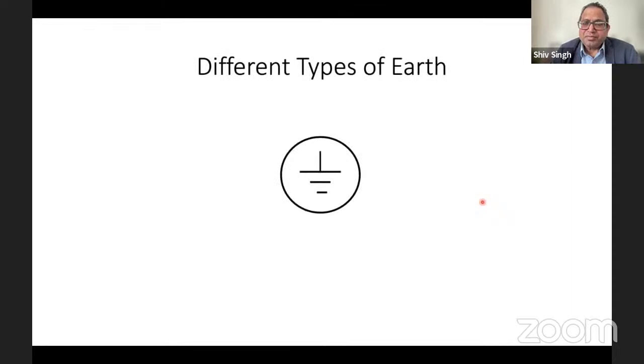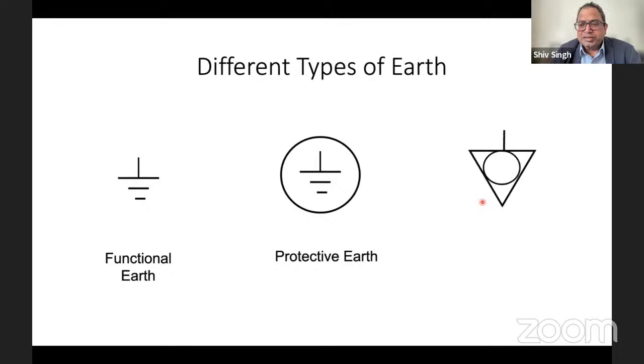So there are different types of earths. That is the normal earth, which is what you actually see. That is called a functional earth. If you see the symbol of an earth in a circle, that's called a protective earth. And then you could see a circle within an inverted triangle, and this is known as equipotential earth. So there are different types of earth. Functional earth is the earth in your socket. Protective earth is the wire connected to the body of the equipment. And I'll talk about equipotential earth in a minute.